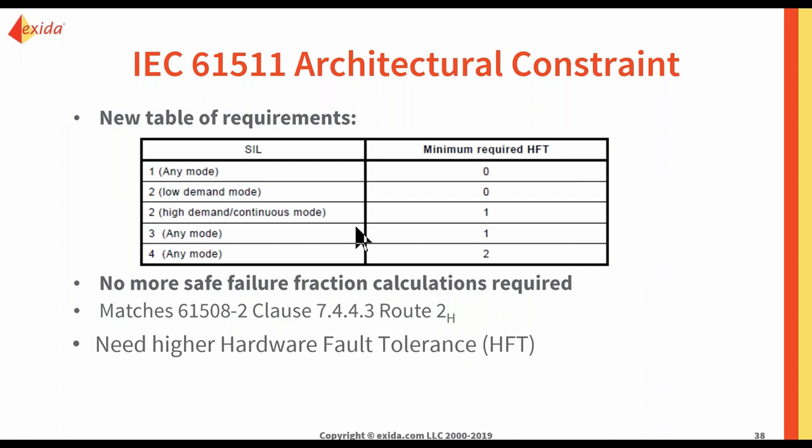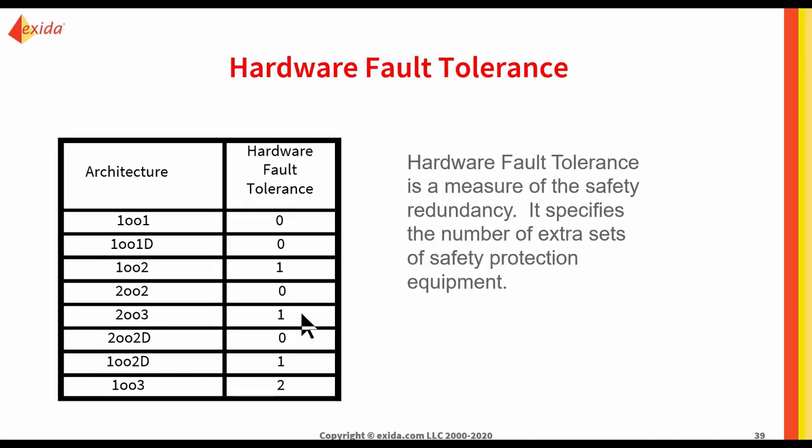I can't go into too much detail about the difference between 1H and 2H, because that is also going to take like 2 or 3 hours. But the easier way to think of it is that in 1H, you need to think about the safe failure fraction for your particular component. But here, you don't really need to consider that, because in the IEC 61511 standard, you only need to look at this particular table. And this is related to something called HFT, the hardware fault tolerance, which is basically your voting.